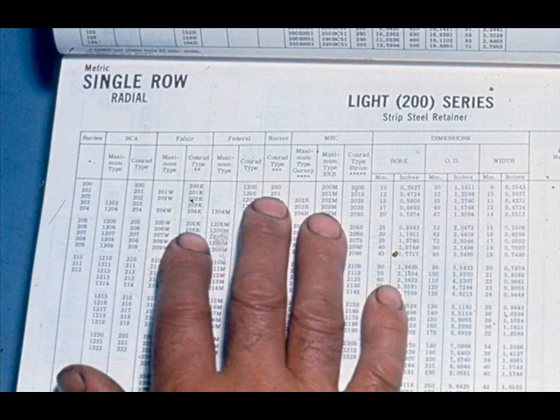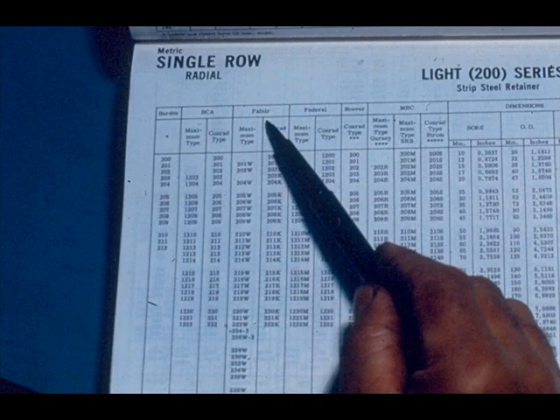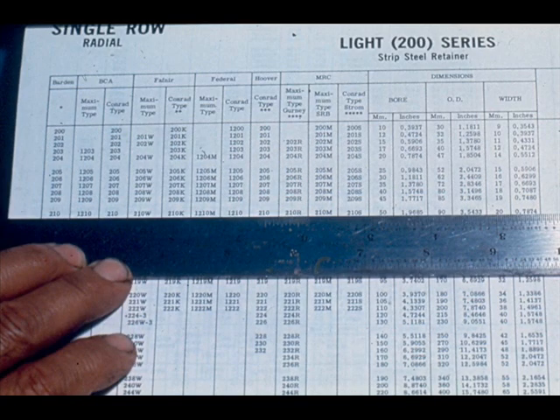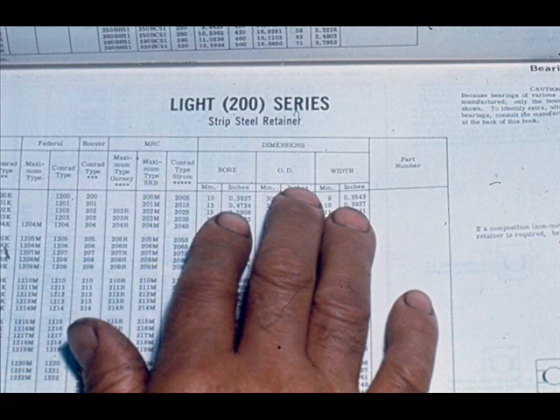The chart on each page will normally be divided into two basic parts. One part will have several columns of manufacturers. Find the column which bears the name of the manufacturer of your bearing, then locate the bearing code number in that column. From this point on, all you have to do is read along the line to the right or left of the number. You will find other bearing code numbers in columns under different manufacturers — all bearings on the same line should be interchangeable with yours. If you can't get an identical replacement from the same manufacturer, you can obtain one from another manufacturer listed.